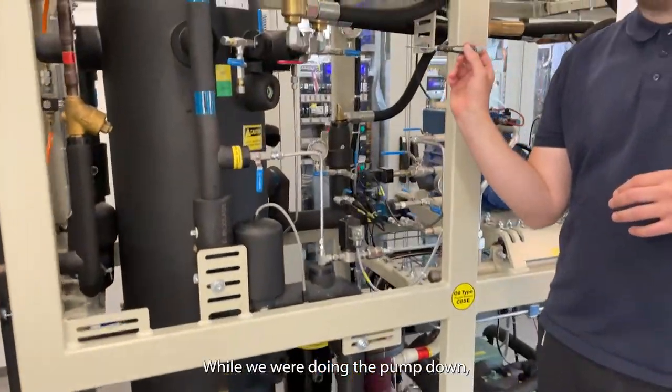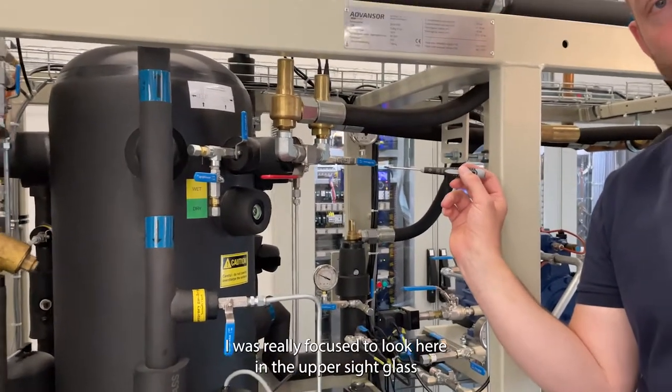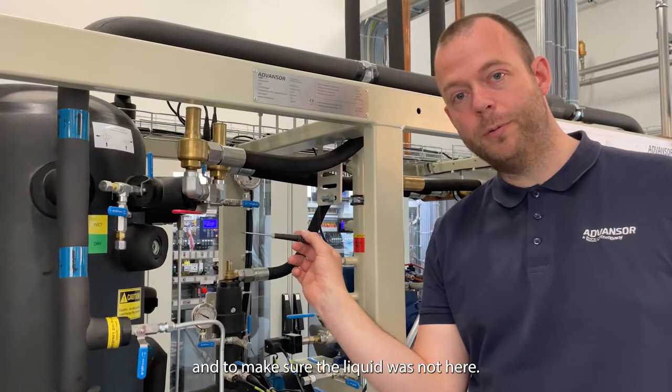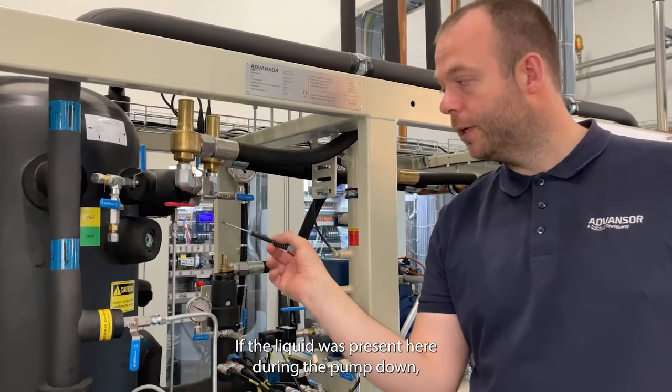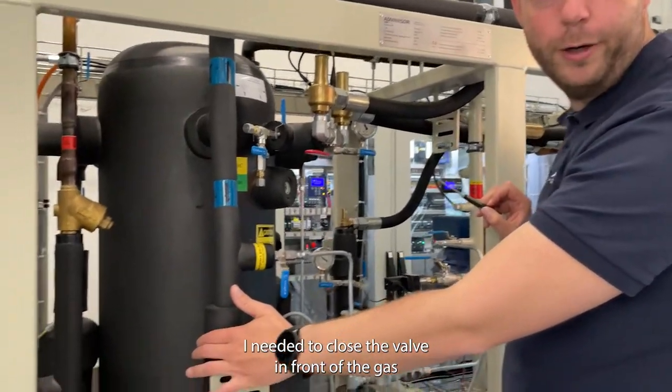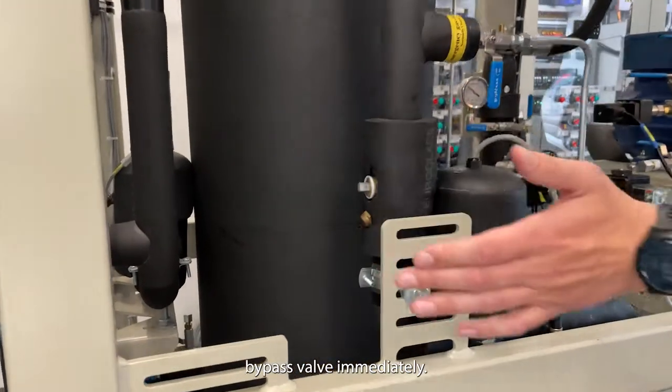While we were doing the pump down, I was really focused on looking at the upper sight glass to make sure liquid was not present here. If liquid had been present during the pump down, I needed to close the valve in front of the gas bypass valve immediately.